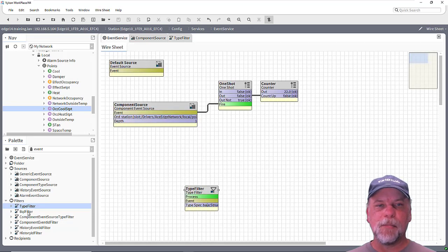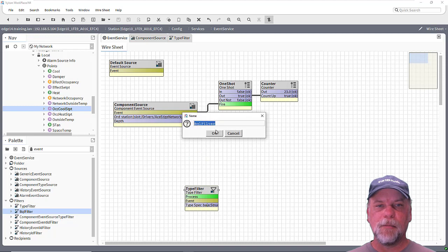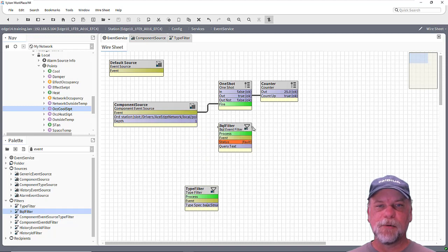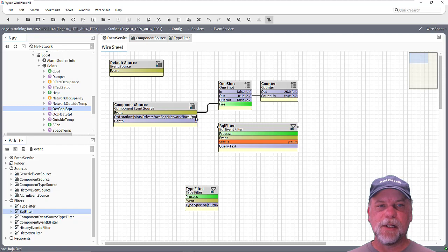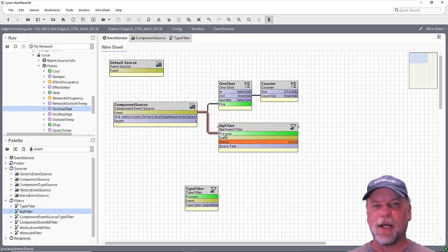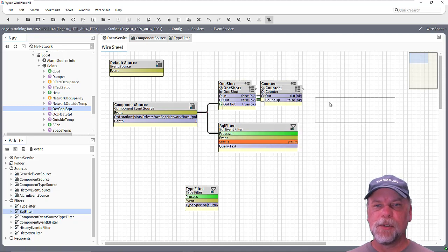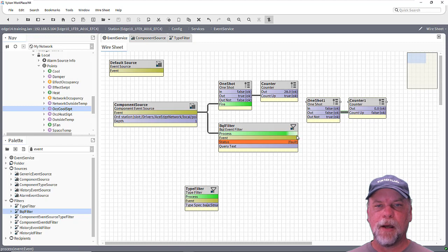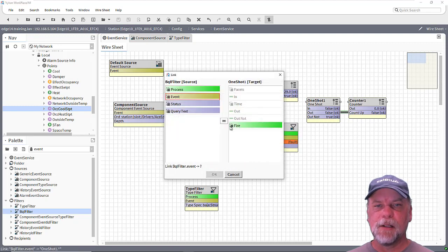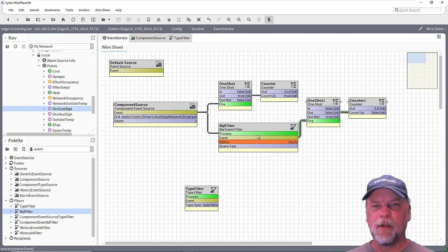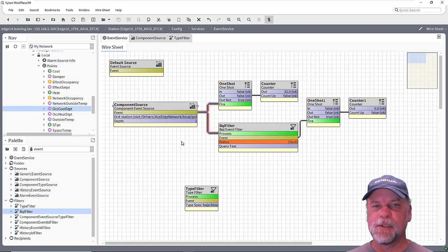We also have a BQL filter. The BQL filter is pretty flexible — it allows us to set up a BQL predicate to filter out things in the events. So we would link the event topic to the process action on the BQL filter. I'm going to duplicate these control points — the one shot and the counter — just so I can see whether the filter is passing the events that are coming into the main component source or not.